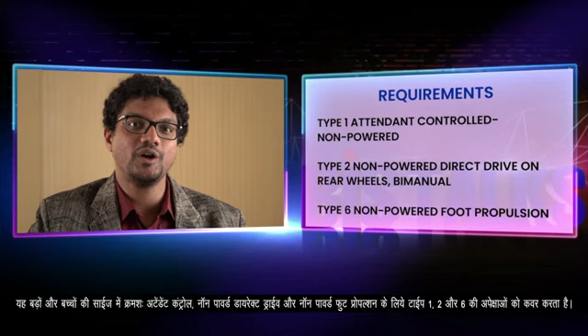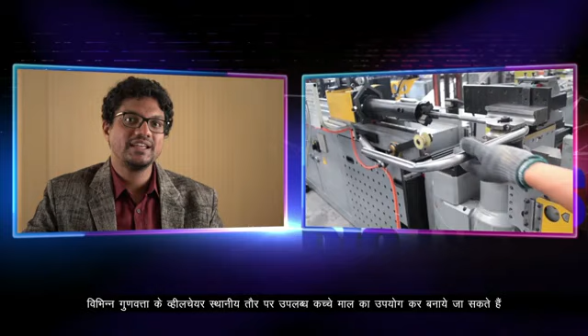It covers the requirements of type 1, 2 and 6 wheelchairs in adult and child size, that is for attendant control, non-powered direct drive and non-powered foot propulsion respectively. The wheelchair can be fabricated using locally available raw materials of variable quality like low carbon mild steel for mainframe, nylon polyester fabric for seat and backrest, vulcanized rubber material for caster wheels, etc. The conformity of the wheelchairs is assessed with tests like stability, load, wheeling, hazard running, folding, impact and drop test, etc. This Indian standard also ensures interchangeability of replaceable components.